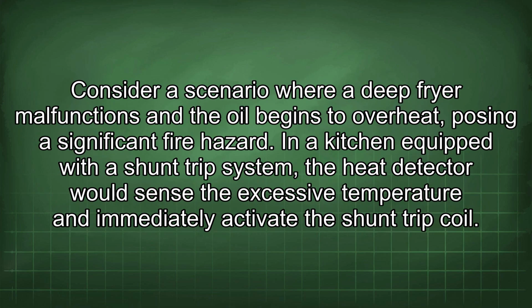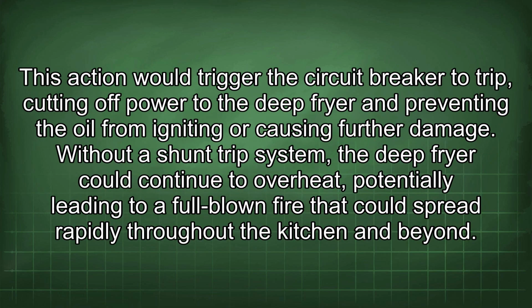occupants. Consider a scenario where a deep fryer malfunctions and the oil begins to overheat, posing a significant fire hazard. In a kitchen equipped with the shunt trip system, the heat detector would sense the excessive temperature and immediately activate the shunt trip coil. This action would trigger the circuit breaker to trip, cutting off power to the deep fryer and preventing the oil from igniting or causing further damage. Without the shunt trip system, the deep fryer could continue to overheat, potentially leading to a full-blown fire that could spread rapidly throughout the kitchen and beyond.